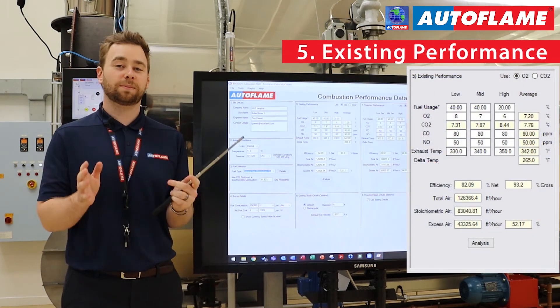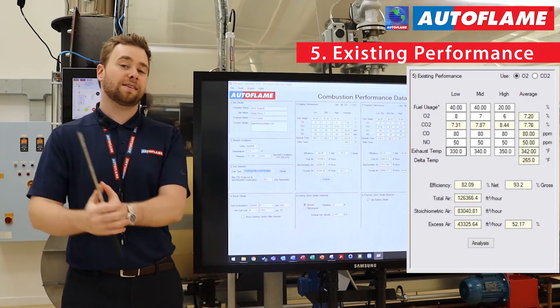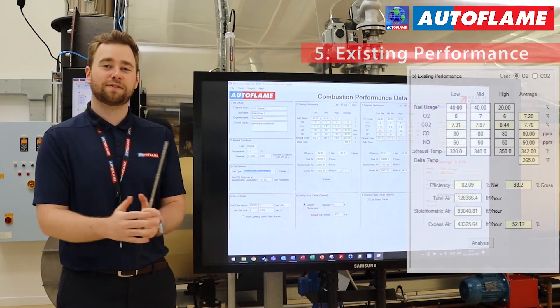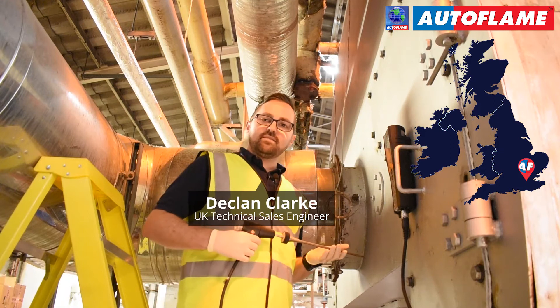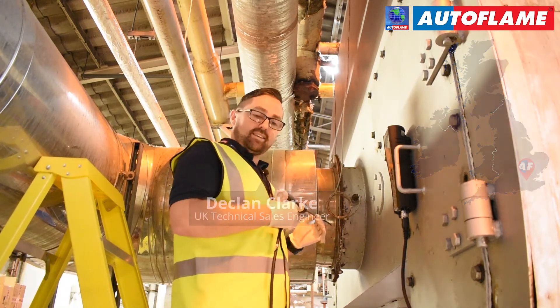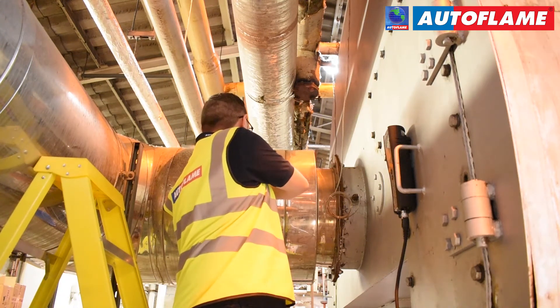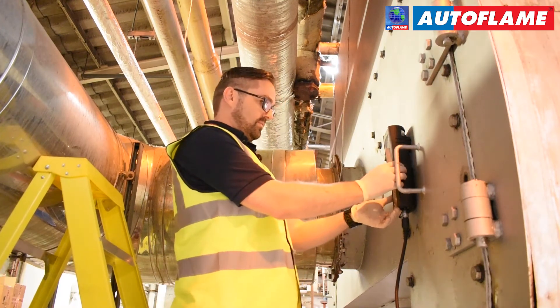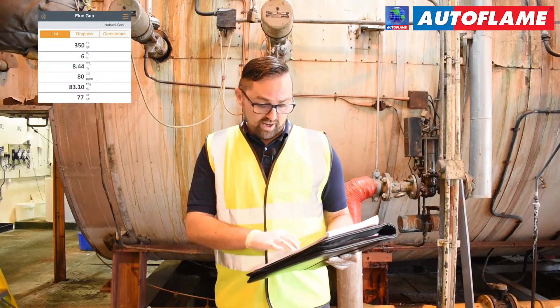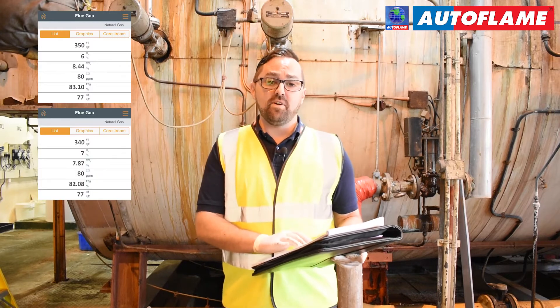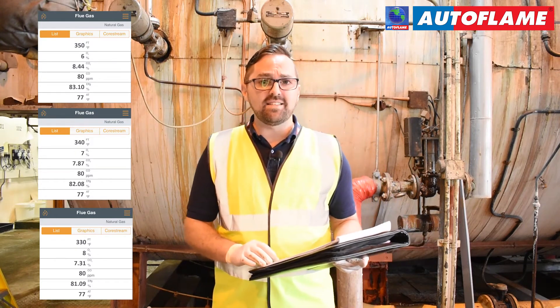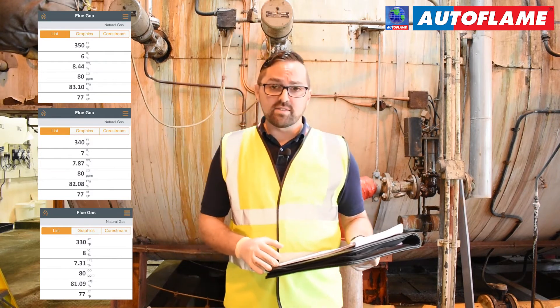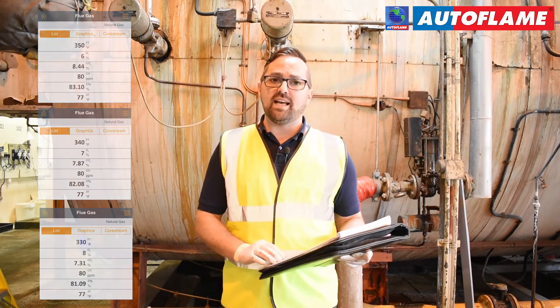Section number five is your existing performance data. We can get this either from information from the customer or we can use Dek, who is on site for us now. The boiler runs off natural gas. Taking readings from the test point in the rear stack: at high fire we were 6% O2, mid fire 7% O2, and low fire 8% O2. Across the firing range the CO is 80 ppm and the NO is 50 ppm. There are real good savings to be made here — it'll be really interesting to see what our emissions calculator has to say.